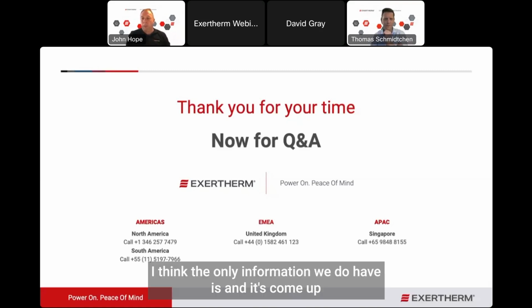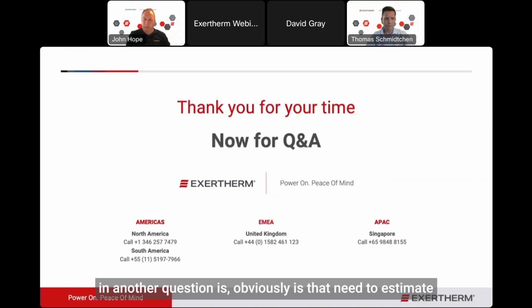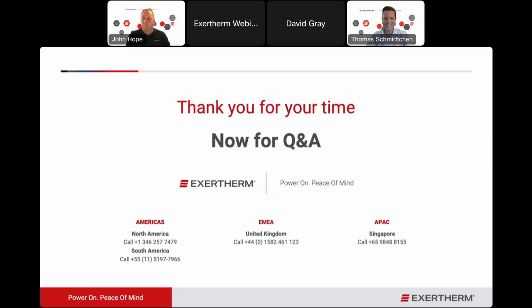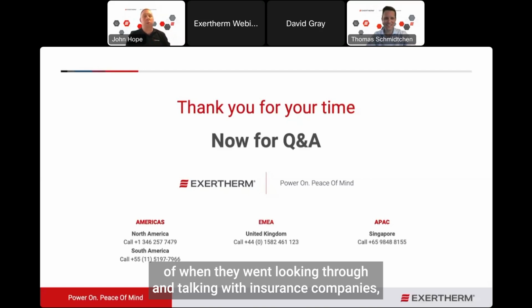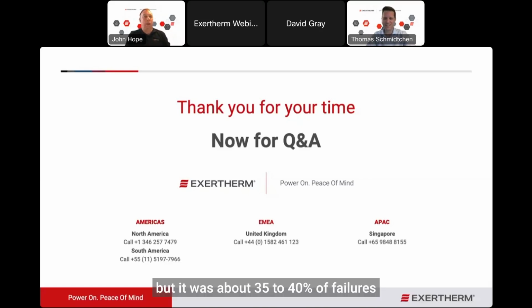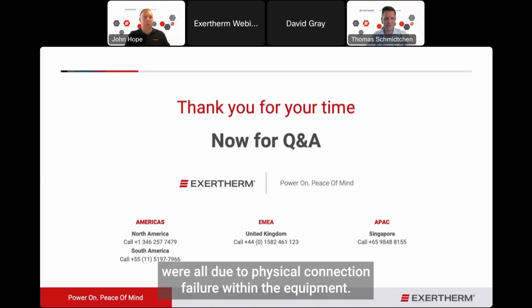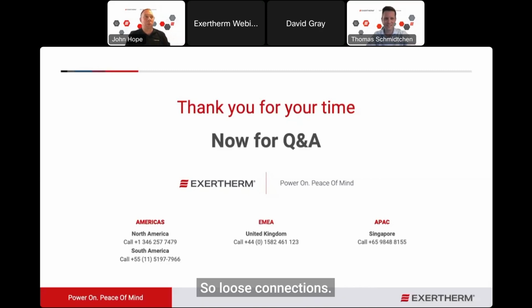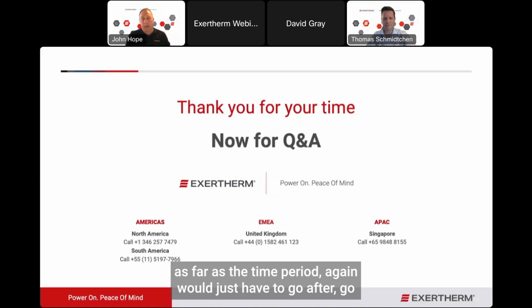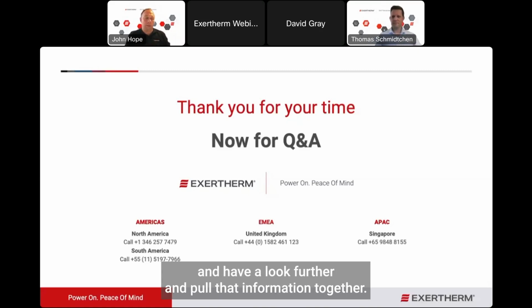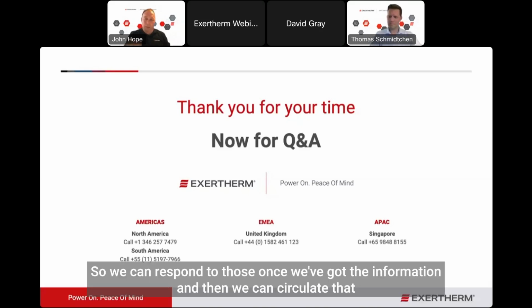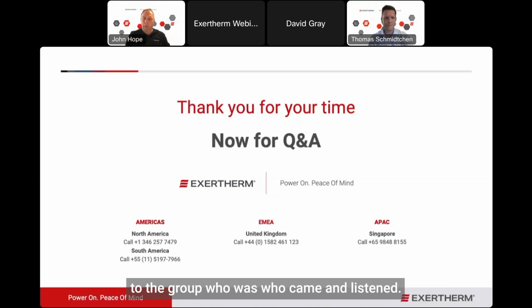I think the only information we do have, and it's come up in another question, is the estimate from when they went looking through and talking with insurance companies, that 35 to 40% of failures were all due to physical connection failure within the equipment, so loose connections. As far as a time period, we'll just have to go and have a look further and pull that information together so we can respond once we've got it, and then circulate that to the group who came and listened.